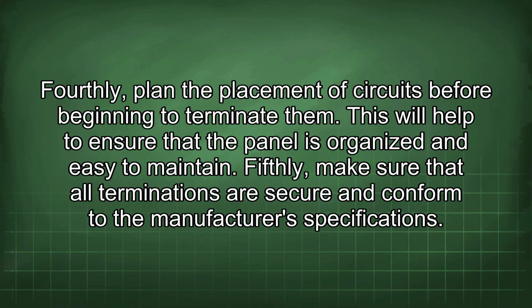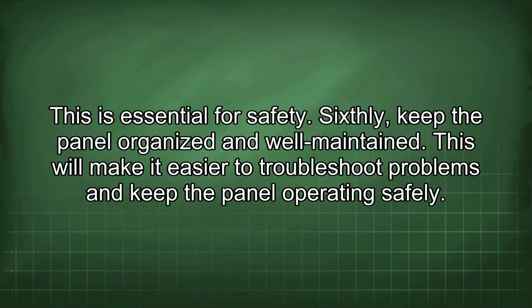Fourthly, plan the placement of circuits before beginning to terminate them. This will help to ensure that the panel is organized and easy to maintain. Fifthly, make sure that all terminations are secure and conform to the manufacturer's specifications. This is essential for safety. Sixthly, keep the panel organized and well maintained. This will make it easier to troubleshoot problems and keep the panel operating safely.